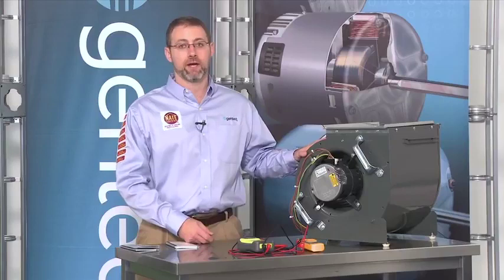You know, when you're finishing any service call, it's a good idea to check all of your wiring, to run the system in all modes of operation, check your safeties, and basically do a quick check of the system that's not going to cause you a return visit. Check your drain traps, your drain lines, set your thermostat back where the customer wants it, and of course recommend annual maintenance. Keep in mind that today most customers probably don't know that you can provide annual maintenance and help keep their filters clean, which is going to keep the system running at better capacity, better efficiency, and provide more comfort to the home. Remember, you're a home comfort specialist.